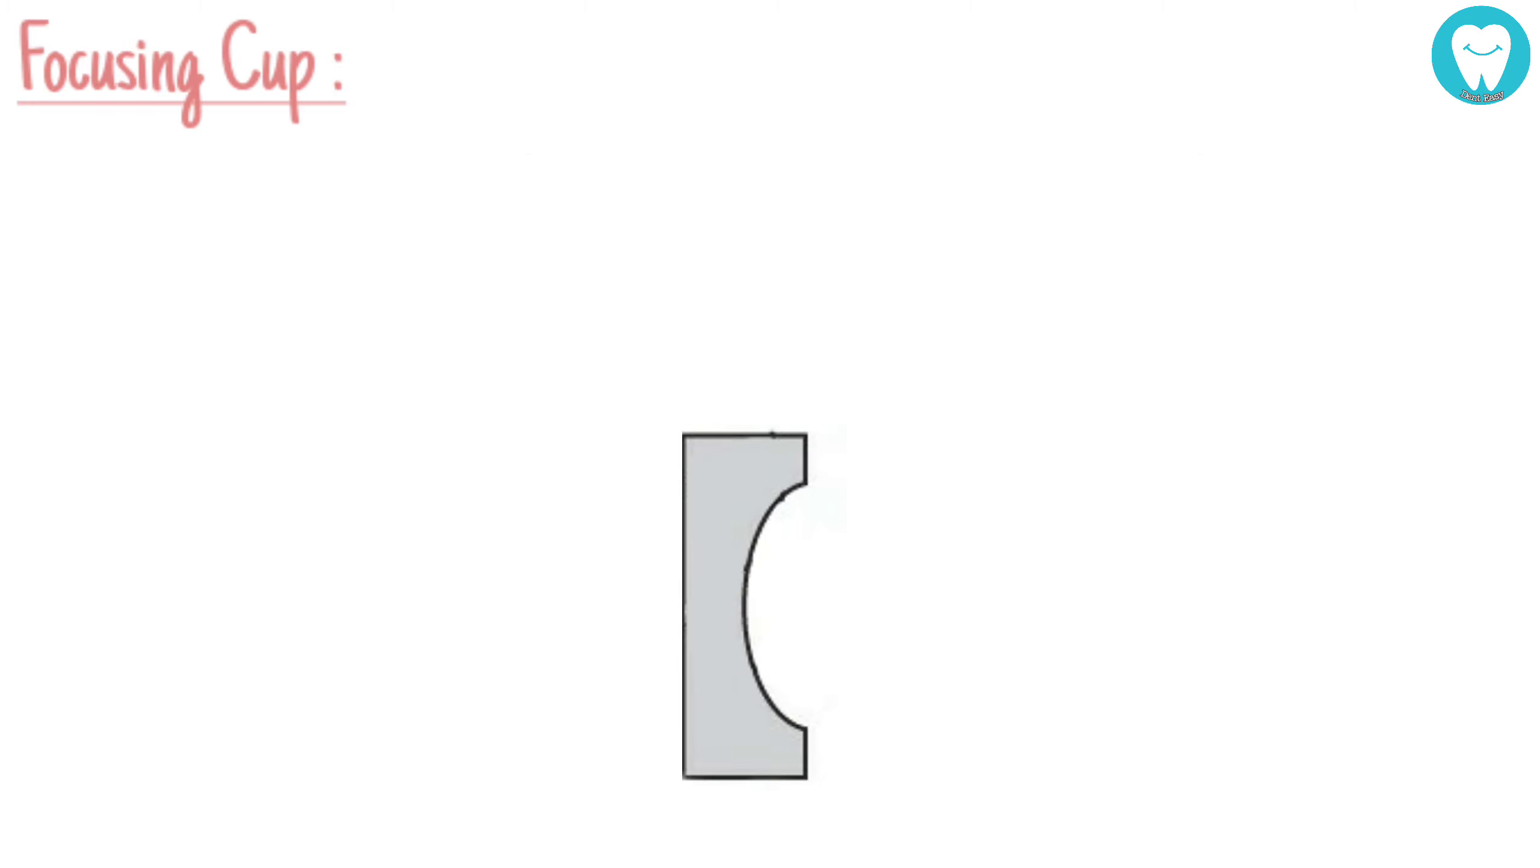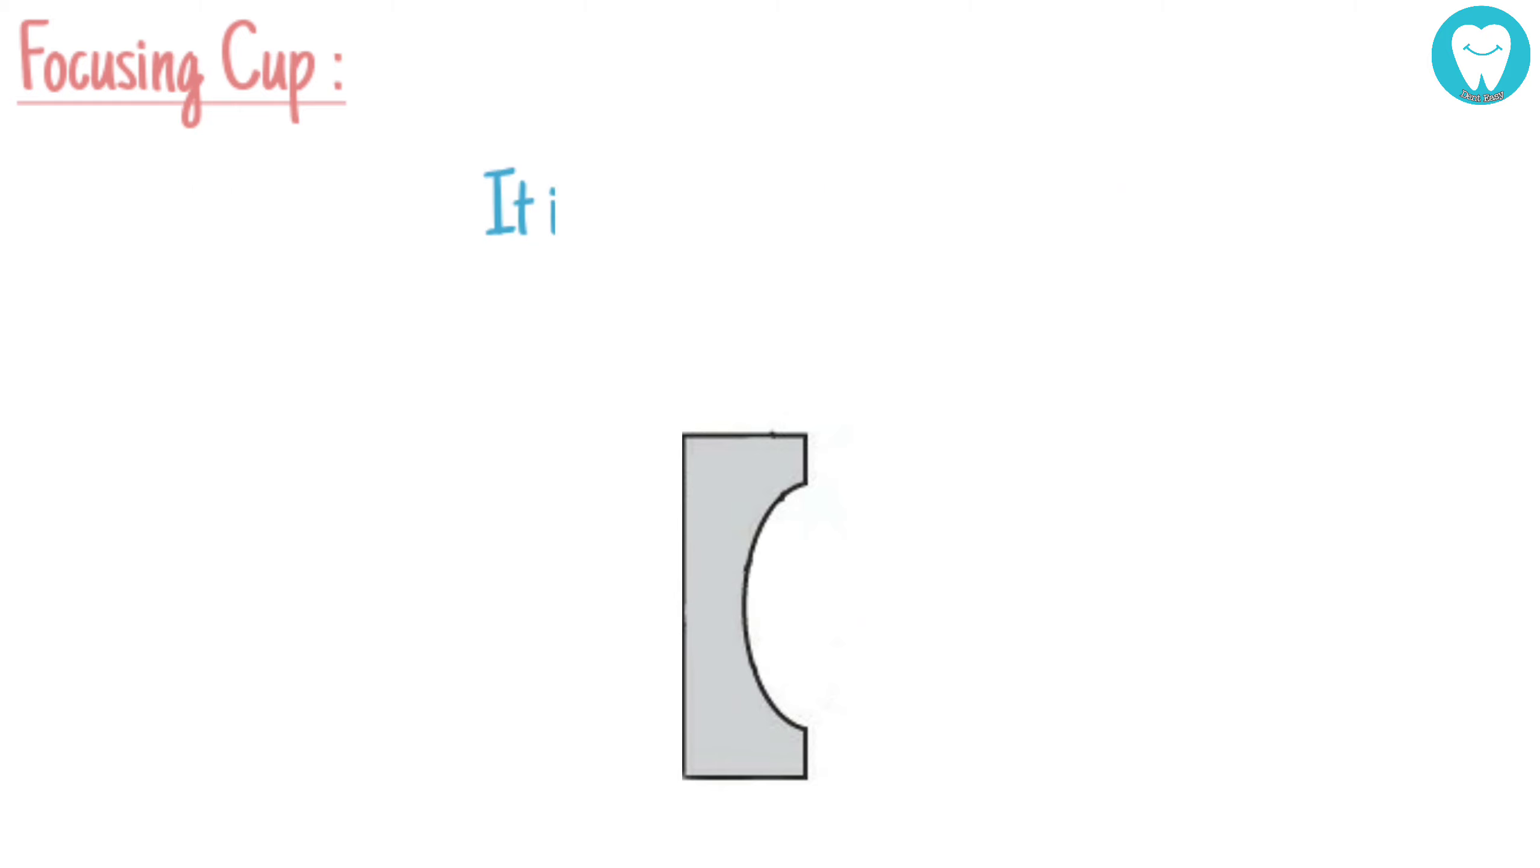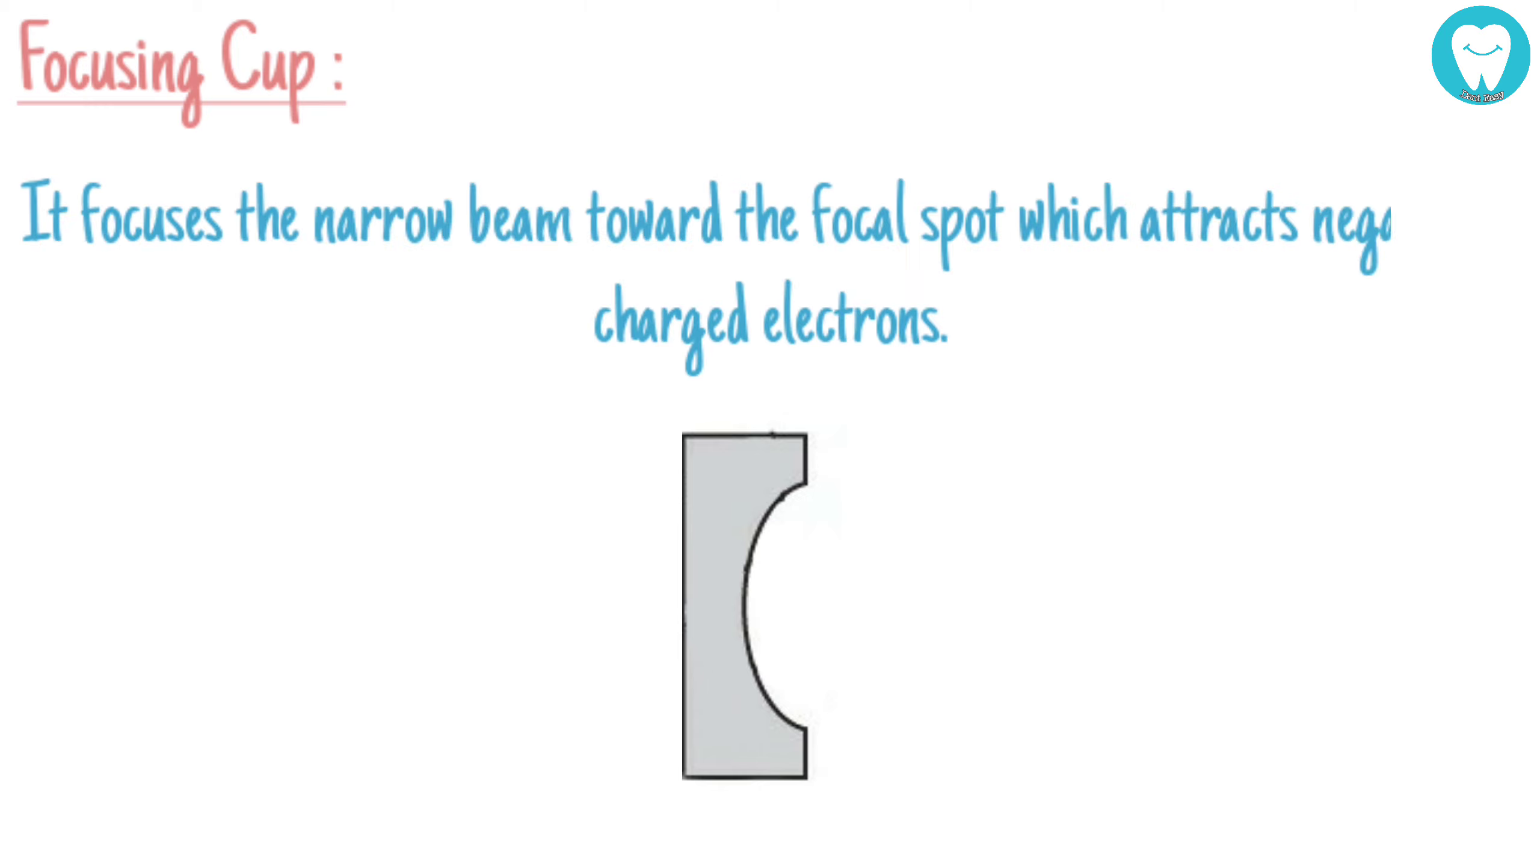The filament is shaped in a slot called the focusing cup, cut into the surrounding metal housing. It is made of molybdenum. It is a negatively charged concave reflector cup that focuses the narrow beam toward the focal spot, which attracts negatively charged electrons.